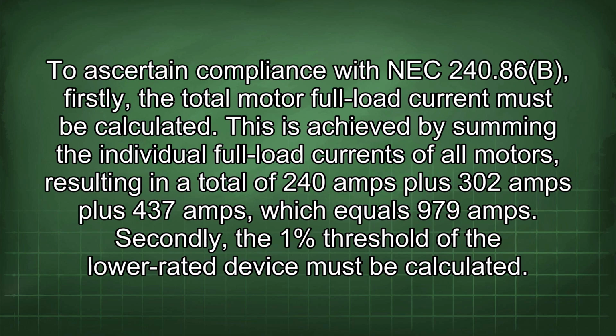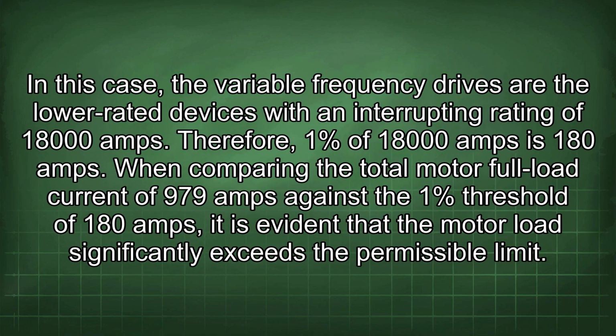To ascertain compliance with NEC 240.86(B), firstly, the total motor full load current must be calculated. This is achieved by summing the individual full load currents of all motors, resulting in a total of 240 amps plus 302 amps plus 437 amps, which equals 979 amps. Secondly, the 1% threshold of the lower rated device must be calculated. In this case, the variable frequency drives are the lower rated devices with an interrupting rating of 18,000 amps. Therefore, 1% of 18,000 amps is 180 amps.